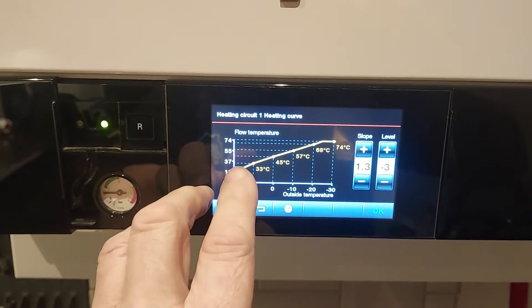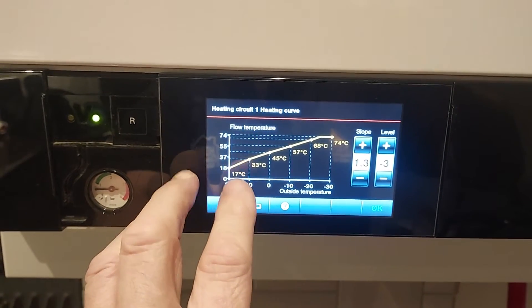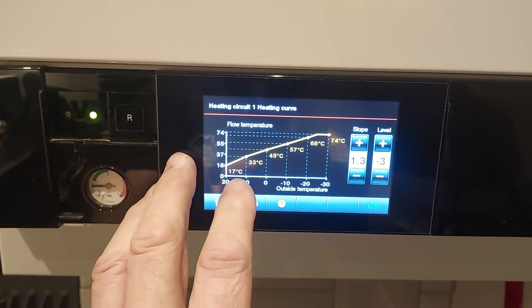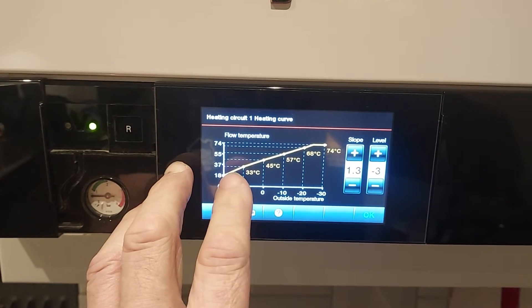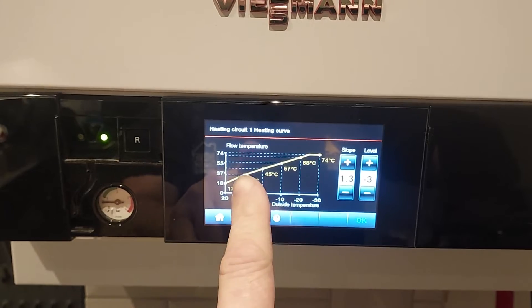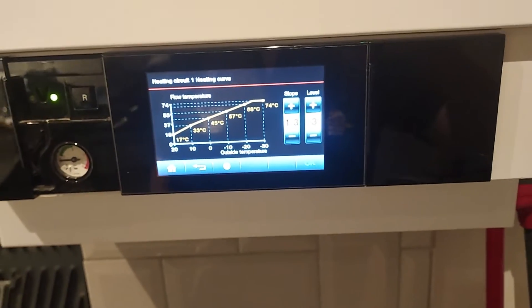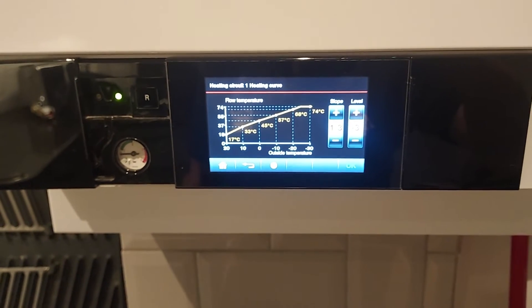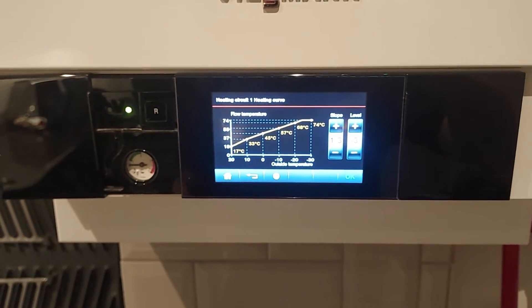So what we've done is dropped this level to bring in the whole heating curve at a lower starting point. You can see here my foot point is actually 18 instead of 20. So somewhere around about 17 degrees outside, that's going to be hitting the 20 degree mark. Below that the boiler should start putting a little bit of heat into the flow to try and maintain the property temperatures. Very stable temperatures in the house and it's doing very well for me.